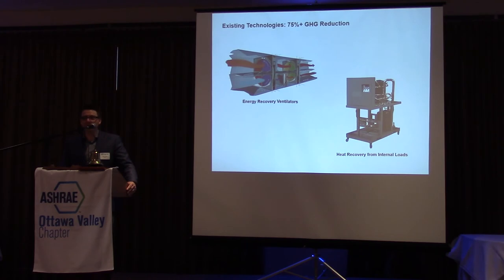Energy recovery on the ventilation side, so heat wheels. And then energy recovery from internal loads, so heat pumps. Heat pumps are our best friends to make sure we're moving energy around within the building, so we're not heating and cooling at the same time. It's not rocket science, but we have tons of buildings heating and cooling at the same time in the middle of winter. We're rejecting heat while also heating the perimeter.